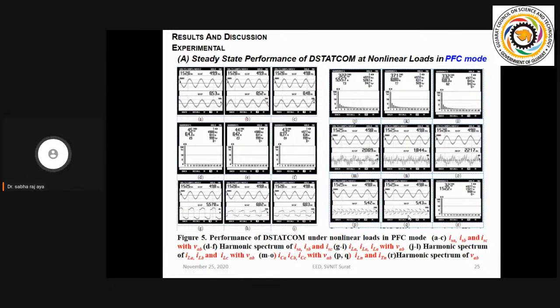If both are equal and opposite, then you are going to see the supply neutral current near zero. At the same time, you can see the level of PCC voltage. Initially, we assumed that our supply PCC voltage is 160 volt. It has gone down to 152. In ZVR mode, we want to maintain 160.